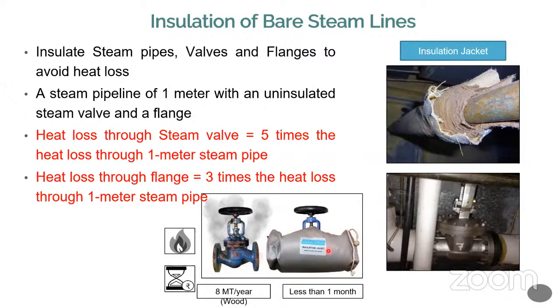Rather than going for this type of insulation, we can go for a TCC painting application. TCC painting application is not only for the flanges and pipes, it can also be used for other areas like this. If you have any problem with the insulation, you can put the TCC painting system. The only thing is it has a life of maximum 2 years.